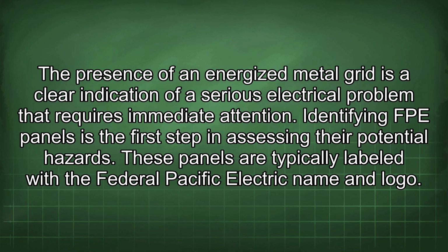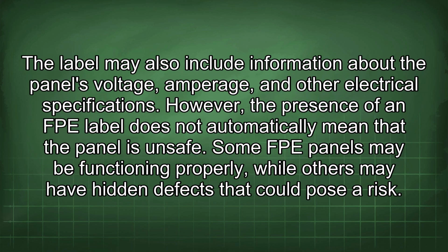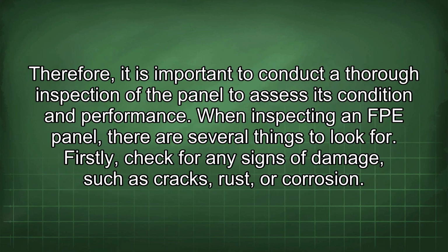Identifying FPE panels is the first step in assessing their potential hazards. These panels are typically labeled with the Federal Pacific Electric name and logo. The label may also include information about the panel's voltage, amperage, and other electrical specifications. However, the presence of an FPE label does not automatically mean that the panel is unsafe. Some FPE panels may be functioning properly, while others may have hidden defects that could pose a risk. Therefore, it is important to conduct a thorough inspection of the panel to assess its condition and performance.